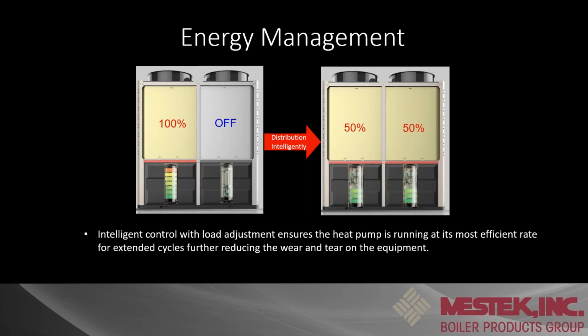And then the energy management. As we're staging, let's say we have multiple units up there, I've got one unit running at 50% capacity on each module, and then I have another unit where one module is off and the other one's running 100%. So it's always looking to match that load based on delivered water temp, and it will stage accordingly.